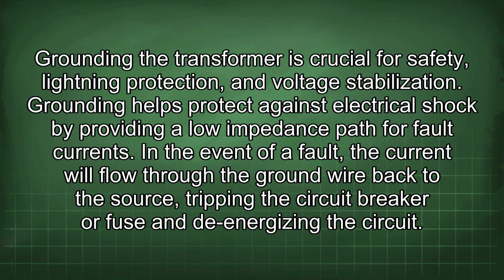Grounding the transformer is crucial for safety, lightning protection, and voltage stabilization. Grounding helps protect against electrical shock by providing a low impedance path for fault currents. In the event of a fault, the current will flow through the ground wire back to the source, tripping the circuit breaker or fuse and de-energizing the circuit.